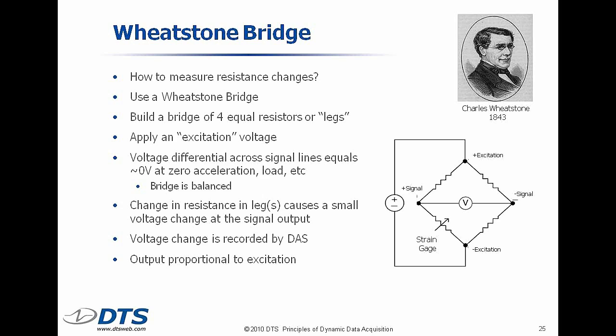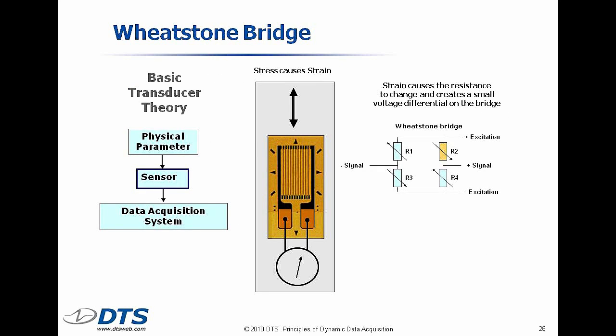So what Wheatstone figured out was if I take 4 resistors and I assemble them into a diamond-shaped bridge, what happens is it's like making 2 voltage dividers, where if I apply a voltage between plus and minus excitation, I will get roughly half the voltage at one signal lead and roughly half the voltage at the other signal lead. And so I can put a very sensitive voltmeter between the two. And then if any one of those resistors changes a tiny bit, I can get a much amplified reading, if you want to call it that. And so the Wheatstone Bridge became the cornerstone of making load cells, accelerometers, all sorts of gauging applications, and it remains so to today.